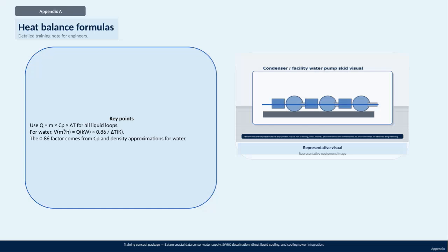In this appendix, we focus on essential heat balance formulas that are crucial for engineers working with cooling systems. One of the key points is the formula Q equals M times Cp times delta T. This is fundamental for calculating heat transfer in all liquid loops. Here, Q represents the heat transfer rate, M is the mass flow rate, Cp is the specific heat capacity, and delta T is the temperature difference.